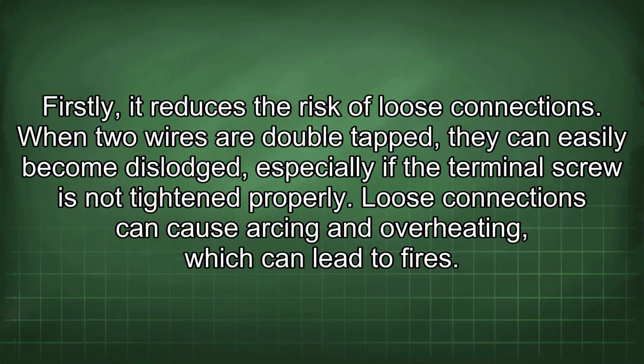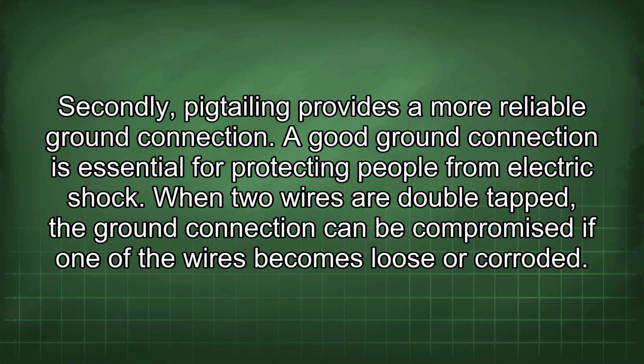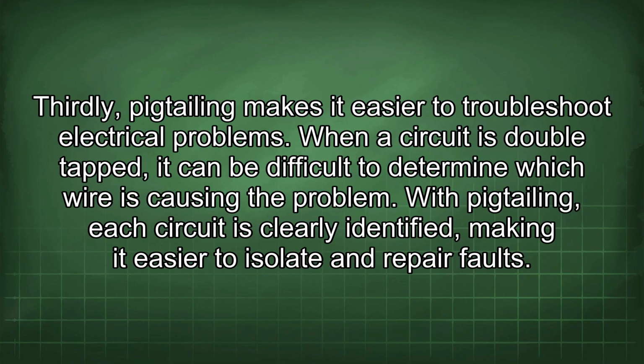Firstly, it reduces the risk of loose connections. When two wires are double tapped, they can easily become dislodged, especially if the terminal screw is not tightened properly. Loose connections can cause arcing and overheating, which can lead to fires. Secondly, pigtailing provides a more reliable ground connection. A good ground connection is essential for protecting people from electric shock. When two wires are double tapped, the ground connection can be compromised if one of the wires becomes loose or corroded. Thirdly, pigtailing makes it easier to troubleshoot electrical problems. When a circuit is double tapped, it can be difficult to determine which wire is causing the problem. With pigtailing, each circuit is clearly identified, making it easier to isolate and repair faults.